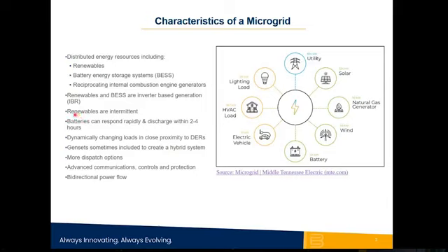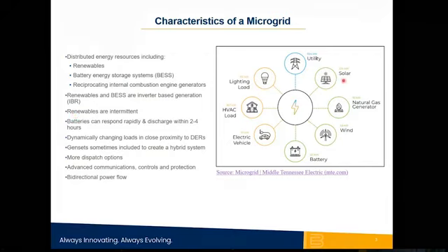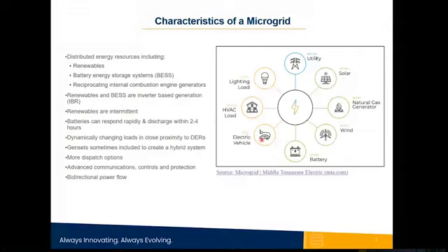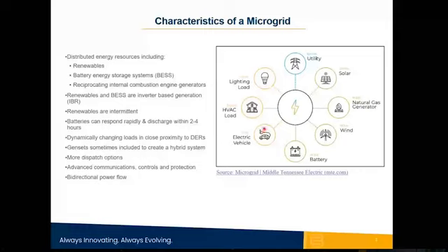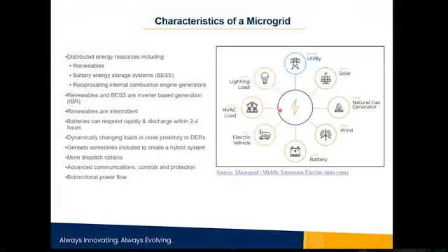Dynamically changing loads in close proximity to the DERs. So for example, here in this system, if this is like a subdivision with all these various resources and loads, and you have multiple EV charging stations, when several EVs are being charged simultaneously, then that adds a huge demand in the local loads. And as a result, the distributed energy resources feel the impact of that. So these dynamically changing loads are something that the power system is not accustomed to seeing, and that has to be controlled and protected in a very unique way for that reason.